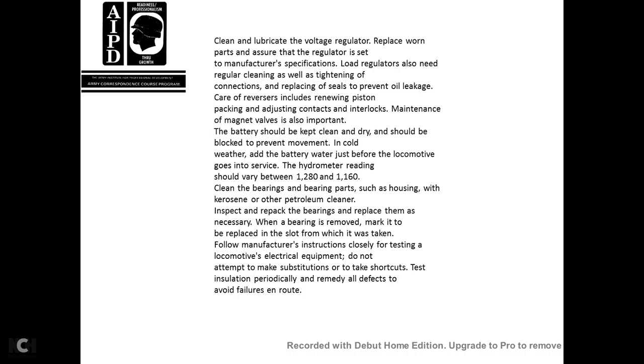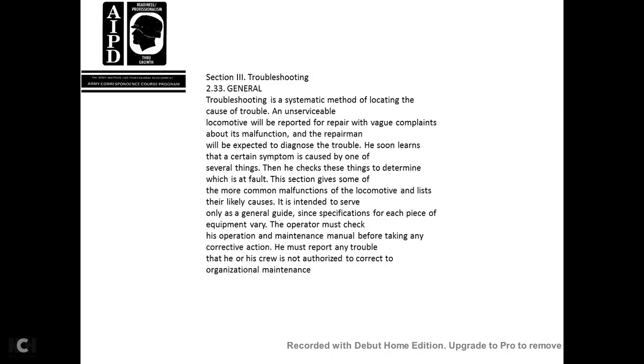Clean the bearings and bearing parts, such as housings, with kerosene or other petroleum cleaner. Inspect and repack the bearings. Replace them if necessary. When a bearing is removed, mark it to be replaced in the slot from which it was taken, following the manufacturer's instructions closely. For the testing of locomotive electrical equipment, do not attempt to make substitutions or to take shortcuts. Test insulation periodically and correct all defects to avoid failures en route.